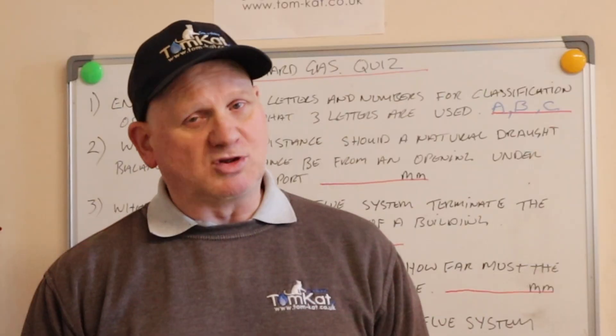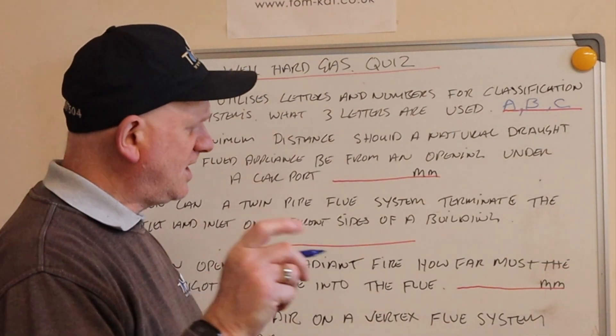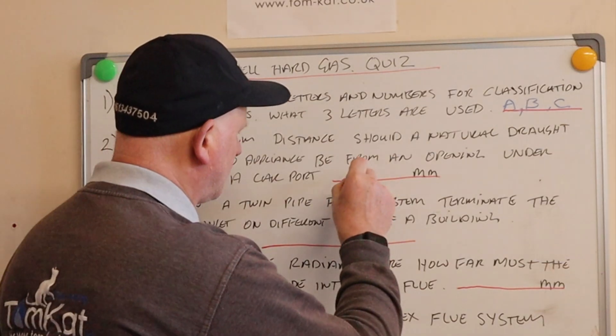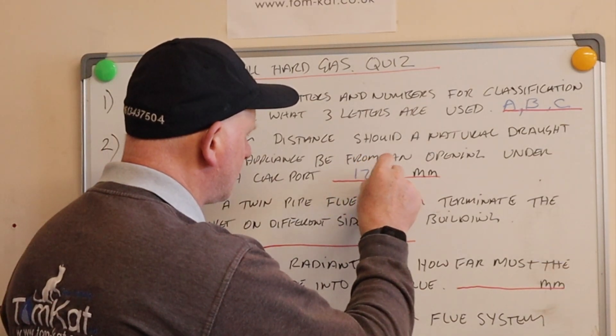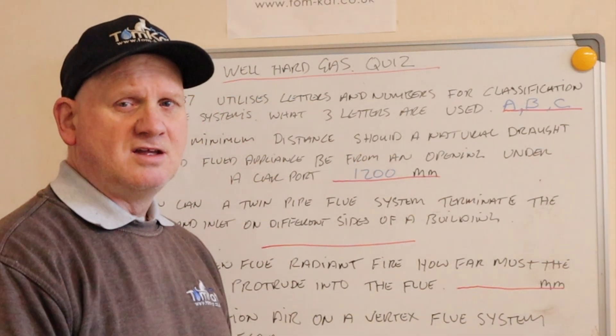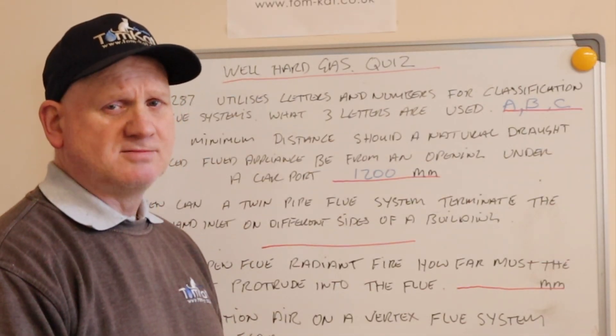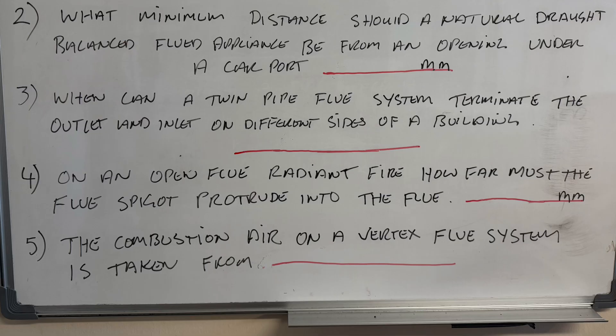Question number two: what minimum distance should a natural draft balanced flue appliance be from an opening under a carport? Hopefully you said 1200 millimeters.